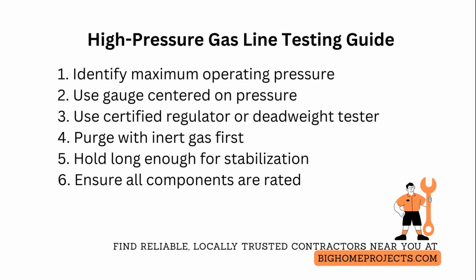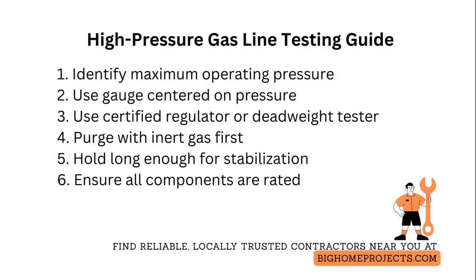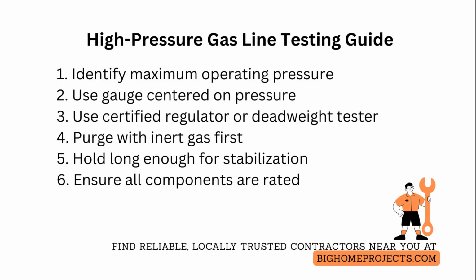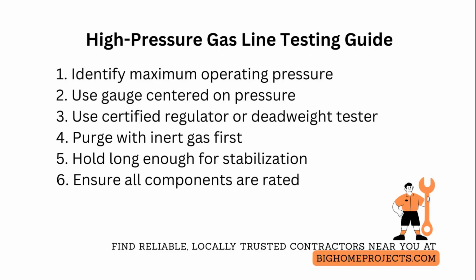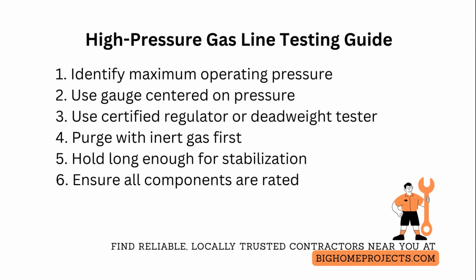Select a pressure gauge with a calibrated range centered on the expected test pressure, so the needle sits in the middle of the dial for best accuracy. For systems above 2 pounds per square inch, choose gauges rated well above the highest test pressure and verify calibration within the past 12 months. Use a high-quality, certified pressure regulator and a deadweight tester or a digital transducer traceable to national standards for the most reliable readings. Avoid low-resolution gauges that can hide small leaks.